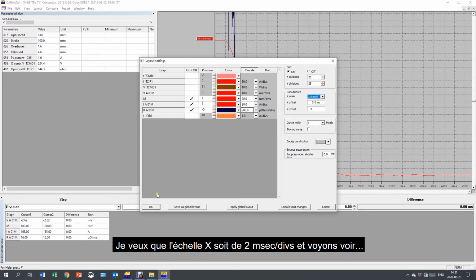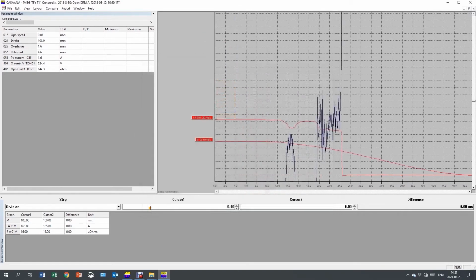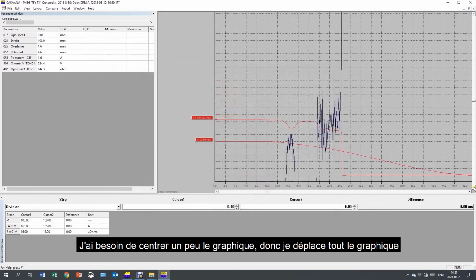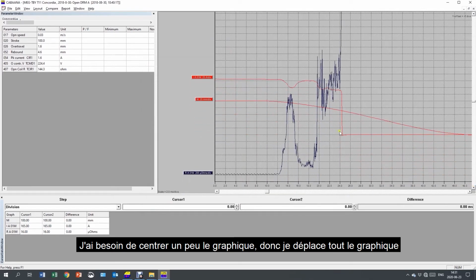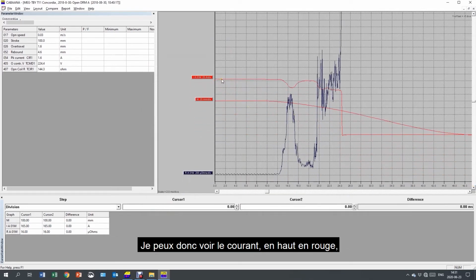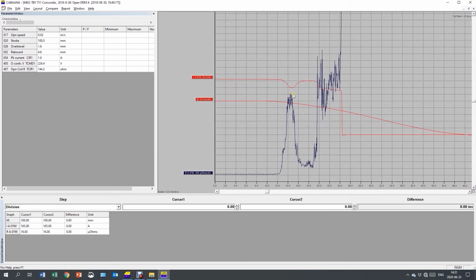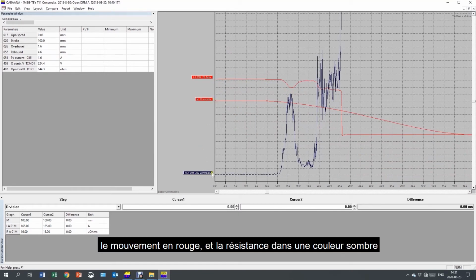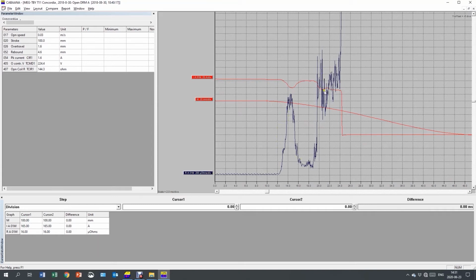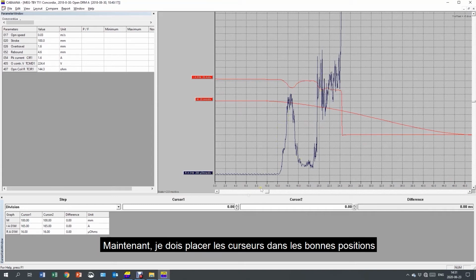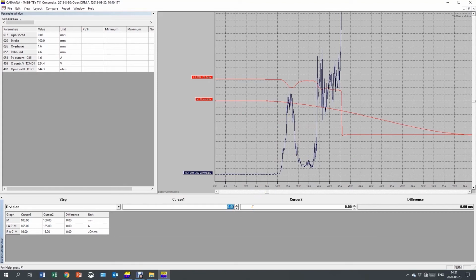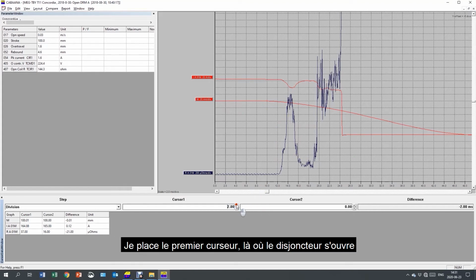And let us see. I need to center the graph a little bit, so I move the whole graph. So I can see the current at the top, red, motion red, and the resistance in a dark color. Now I need to put the cursors in the right positions. I put the first cursor where the breaker opens. And that is where the current drops at around 24 milliseconds. I needed to move it exactly to the dropping point there.